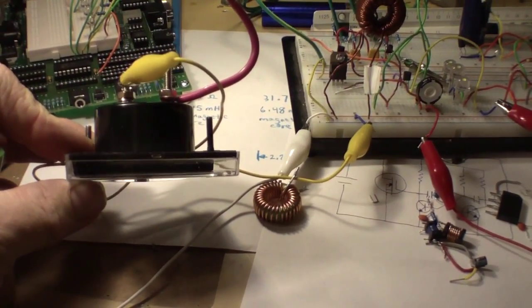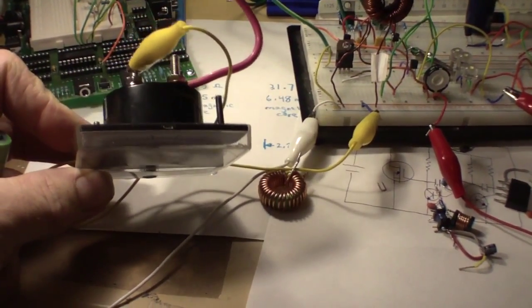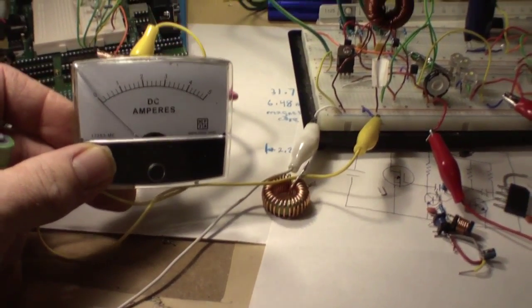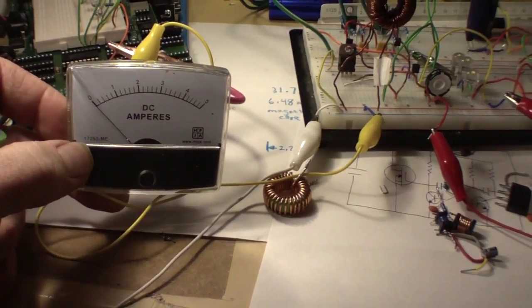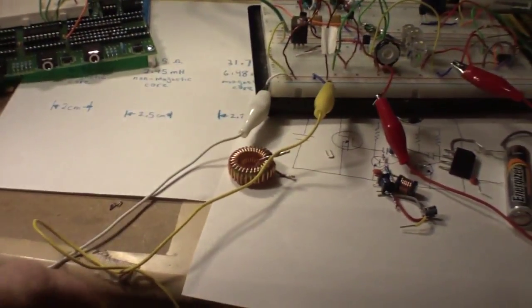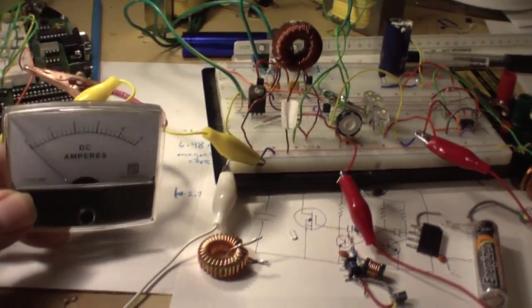Really what you're doing is measuring the millivolts — or the volts — across the shunt. The shunt is filed; tiny extra strokes are taken off of it to ensure its accuracy. If you buy from one brand you probably get better quality control than another. But at the end of the day when you put this thing in line, you're doing exactly what other people, sites, books, and texts are telling you to do.